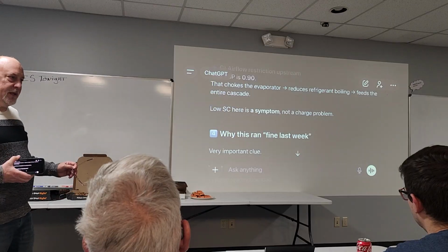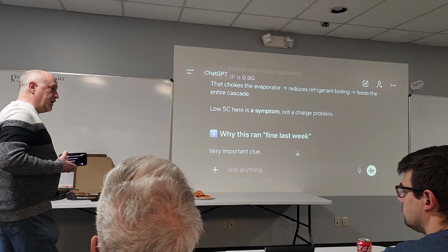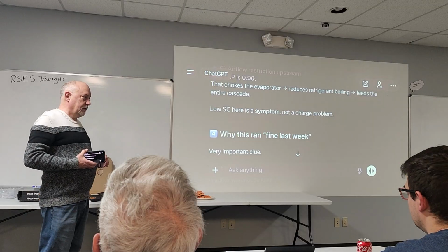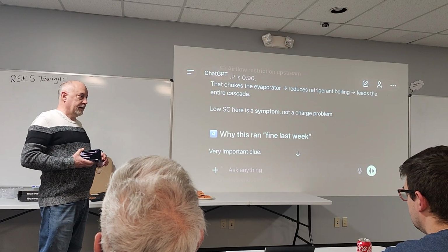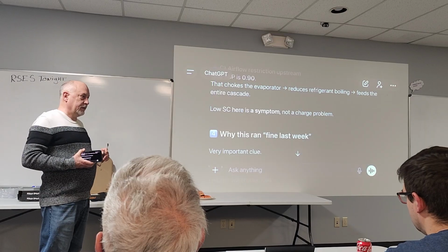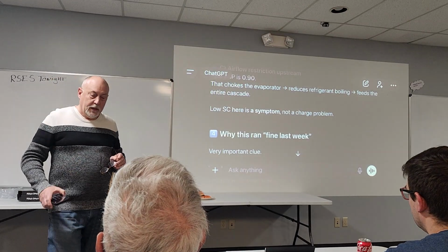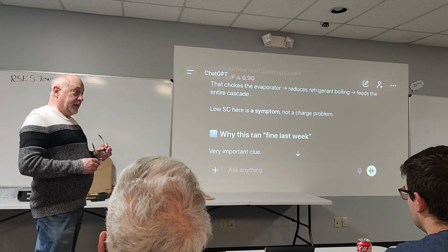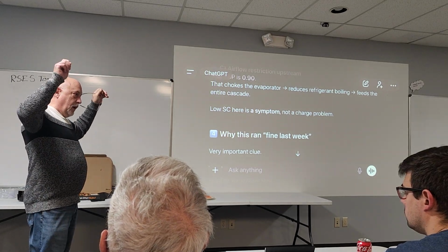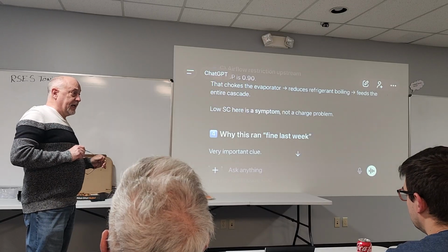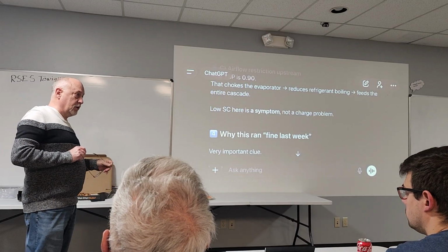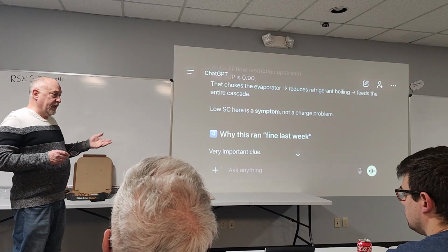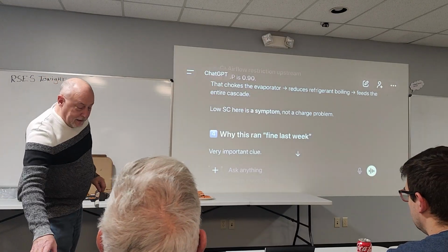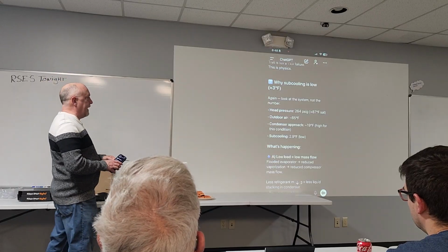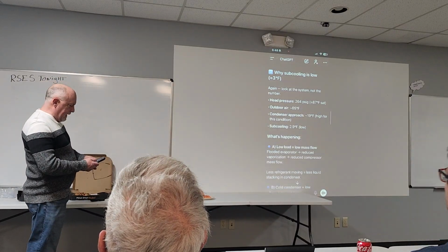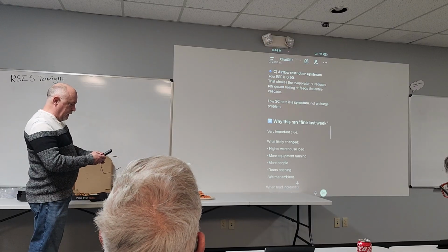Just think about what happens here. We have a piston system, and you nailed it. What did you say was wrong with this? You said two things: low airflow and a dirty condenser. Yeah, low airflow and a dirty condenser. Which is exactly right, because what I did is I went out in my shop and I actually blocked the airflow off with a damper, so I blocked my supply down to create high static pressure. I have a rheostat on my condenser fan, and I slowed my condenser fan way down to create effectively a dirty condenser, right? Now, what it's saying here, let me go back to where that was: low load, low airflow.